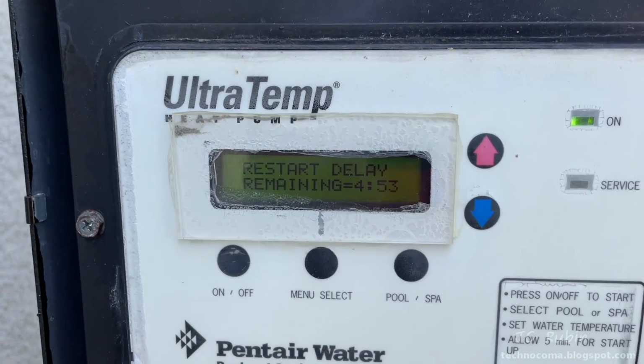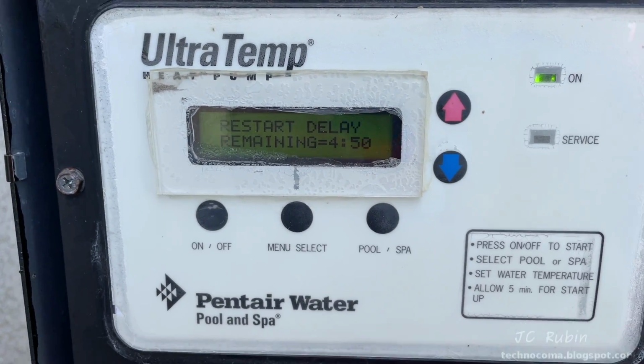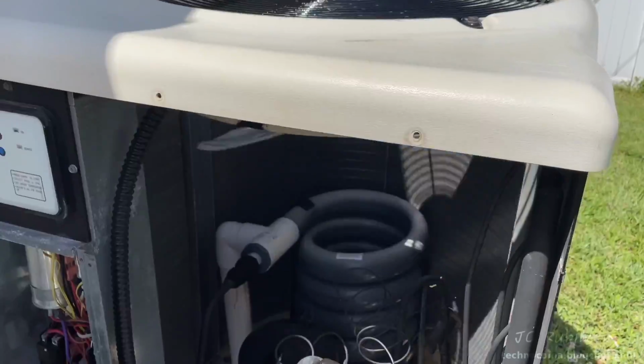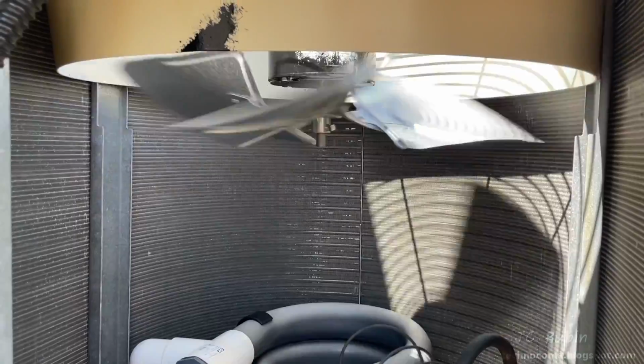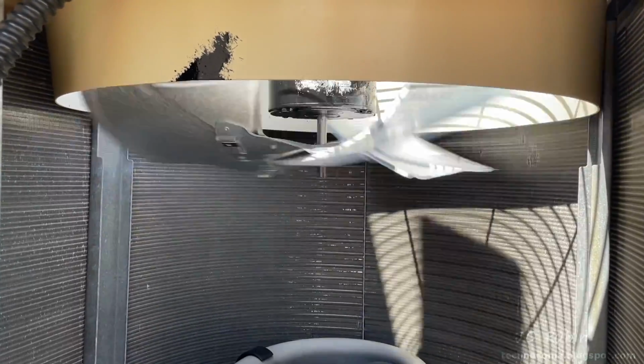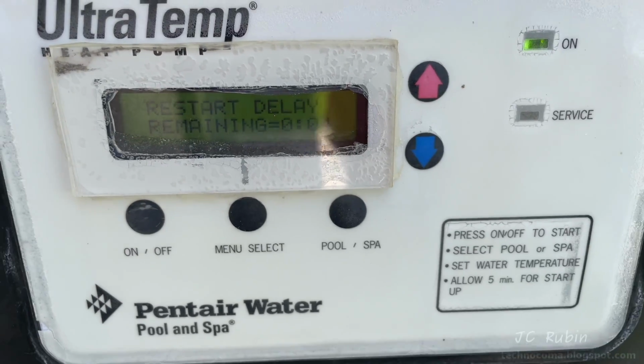It'll stay like this for 5 minutes before the compressor kicks in. Everything sounds good, no vibration, no excessive noise. The blades look relatively balanced, I don't see any wobble. The compressor will kick on in 5 seconds.